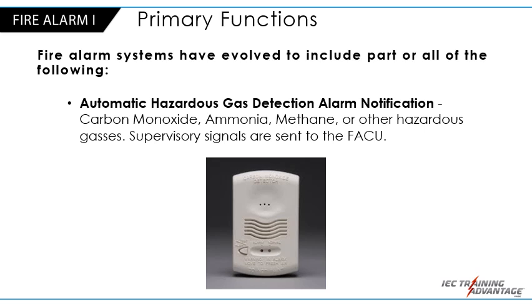Automatic hazardous gas detection alarm notification. Carbon monoxide, ammonia, methane, or other hazardous gases are all dangerous to occupants inside of a building. These detectors send signals to the FACU saying, hey, there's presence of carbon monoxide or ammonia or these other hazardous gases. They send a supervisory signal to the FACU to allow the FACU to notify the occupants, hey, you need to evacuate. There's a gaseous issue in the building and you need to get out for your own safety.